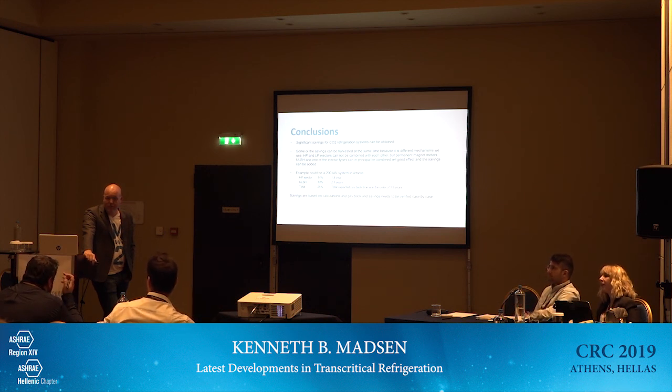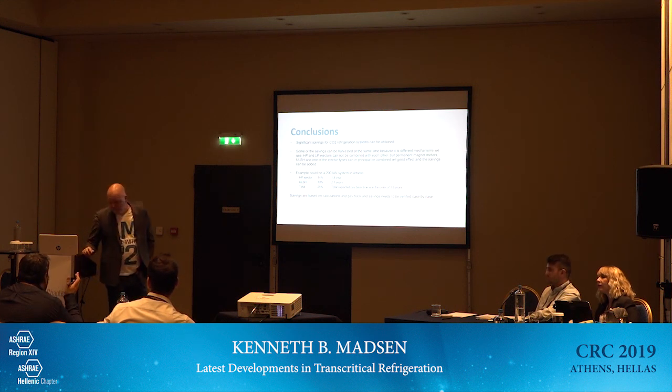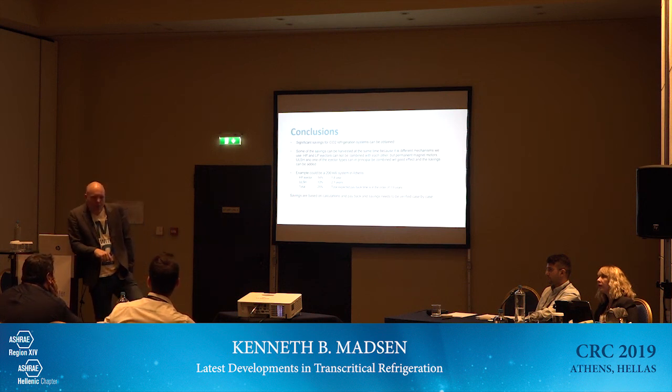For the ultra-low superheat, how do we achieve it? Just set the controller to be at one superheat? That is a little bit different from controller manufacturer to controller manufacturer.